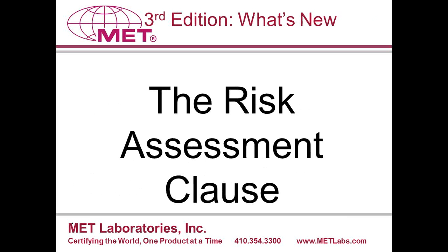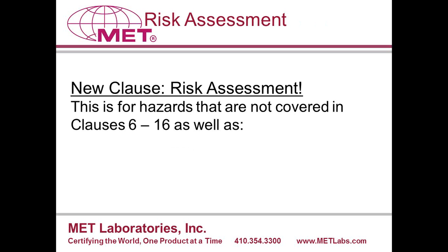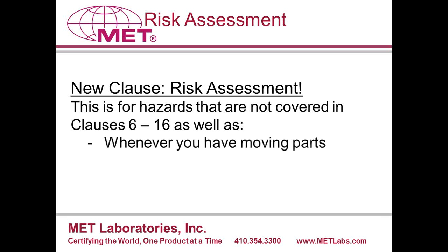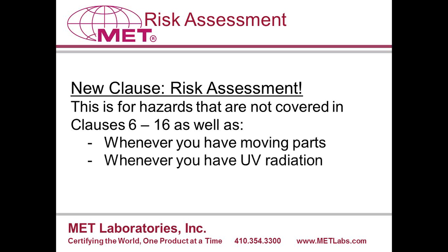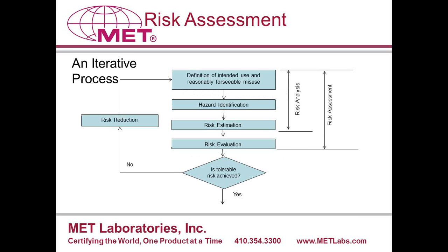The final change in 61010 third edition is the addition of a new clause and new concept, the risk assessment. Risk assessment is meant to cover hazards that may arise from technological aspects of a product that are not already covered in the standard, but which may cause harm. It should also always be used whenever there are hazardous moving parts or radiation exposure hazards. Risk assessment is an iterative process because a particular measure of risk reduction may not lower the hazard to a tolerable level. If not, you need to look at other means of reducing the risk of hazard.